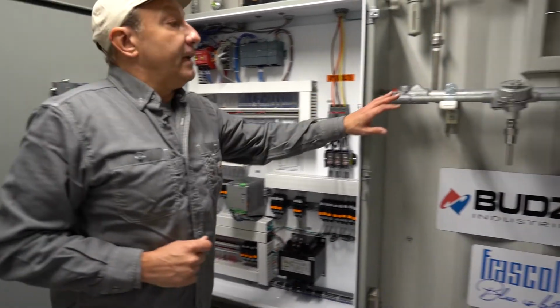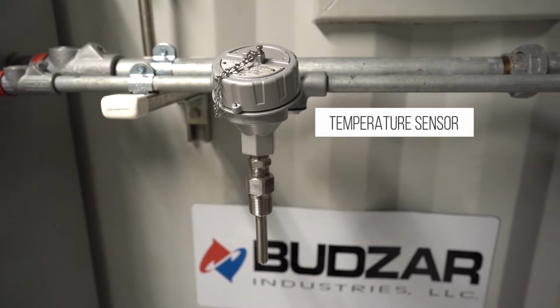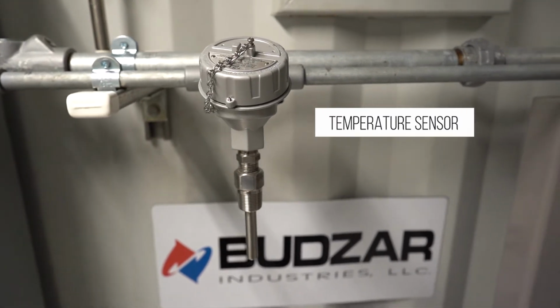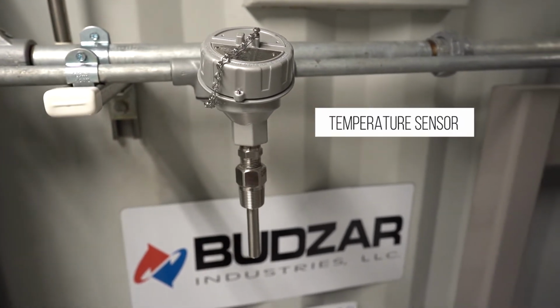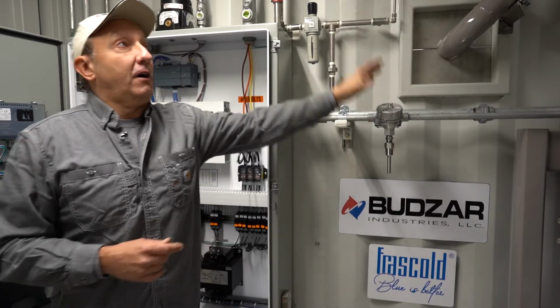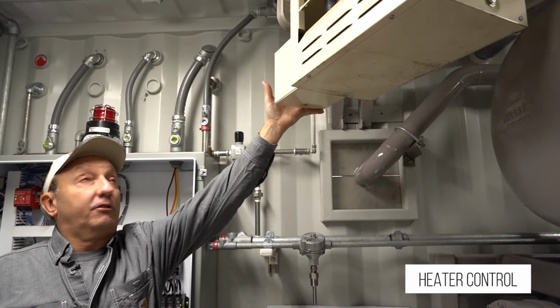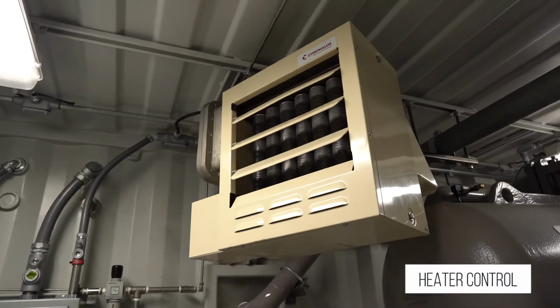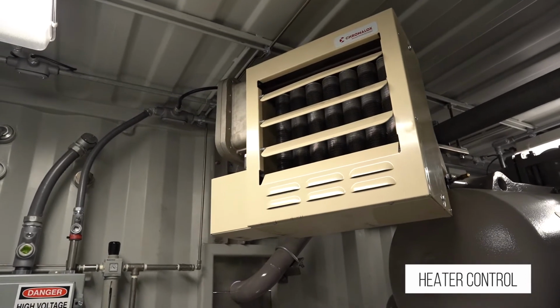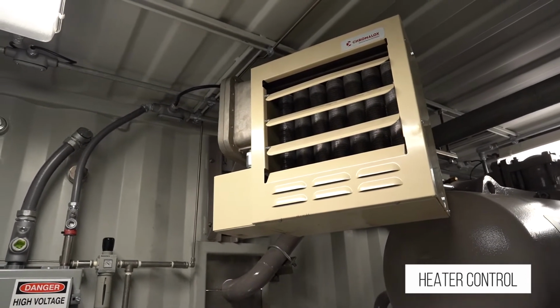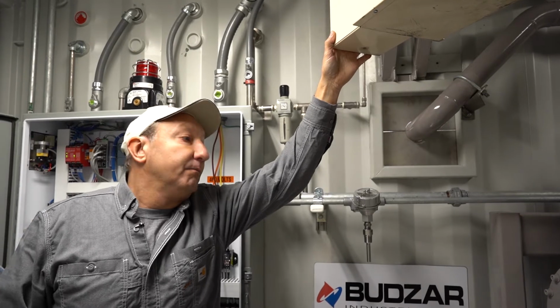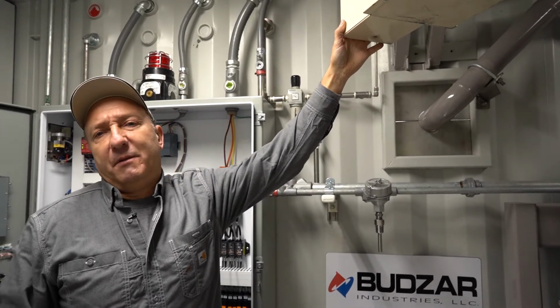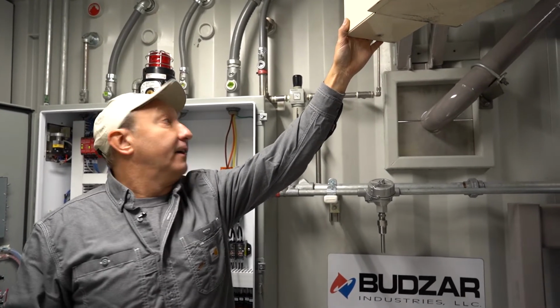Over here, we have our temperature sensor, a PT100 3-wire RTD. This measures the ambient temperature inside the cabinet for our heater control. These are also explosion proof because of the volatility of the propane. And we have 3 of these located in the container to maintain warm temperature. We have them set for about 65, 70 degrees Fahrenheit.